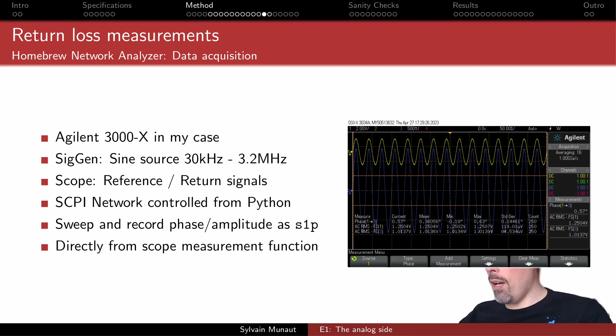The script performs the sweep and records the phase and amplitude results directly from the scope measurement function, and they're recorded as S1P, like an S1 parameter file. Those data are loaded into the scikit-rf Python package, and that package is pretty neat because first it can handle all the plotting, loading the data file and all the plotting, and it also handles the short open load calibration math. So I can do a sweep for a short, a sweep for an open, a sweep for an ideal 120 ohm, feed that, and it will actually compute calibration coefficients to try to remove the imperfection from the system.